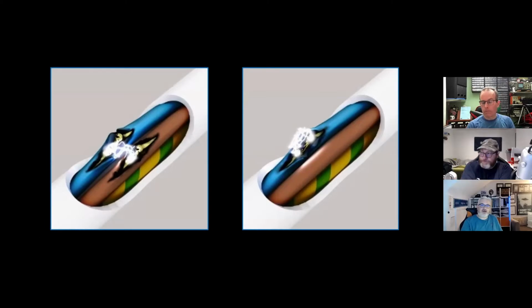There could be small damage causing leakage between conductors, which wouldn't be picked up by an RCD, but would do sufficient damage to allow carbon to deposit as the PVC breaks down. That carbon becomes the fuel. As the copper melts, it oxidizes, forming a gas - a source of ignition. If it's over 2.5 amps, boom, you've got the perfect recipe for a fire.